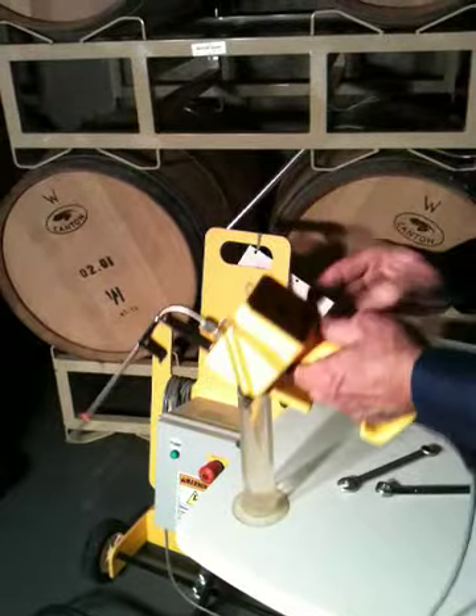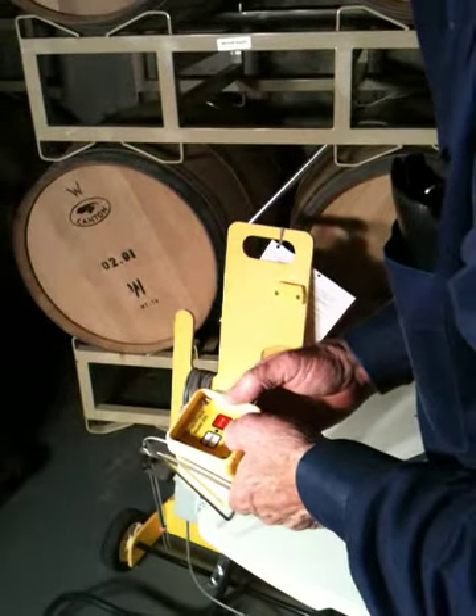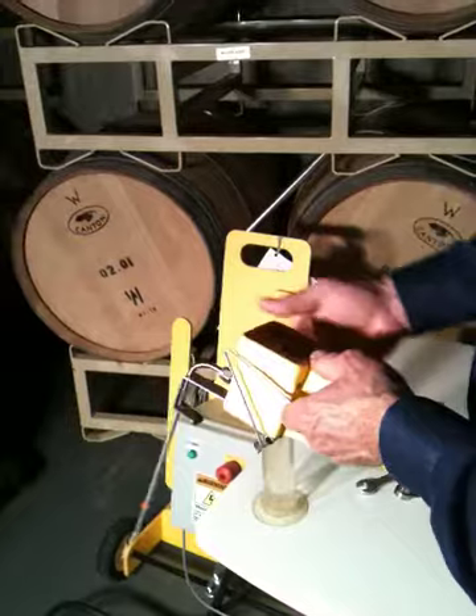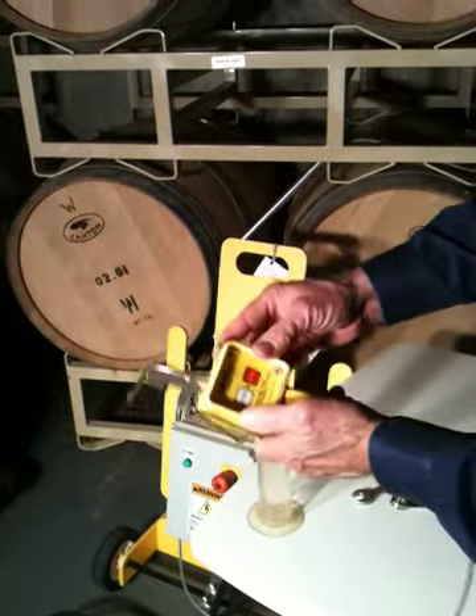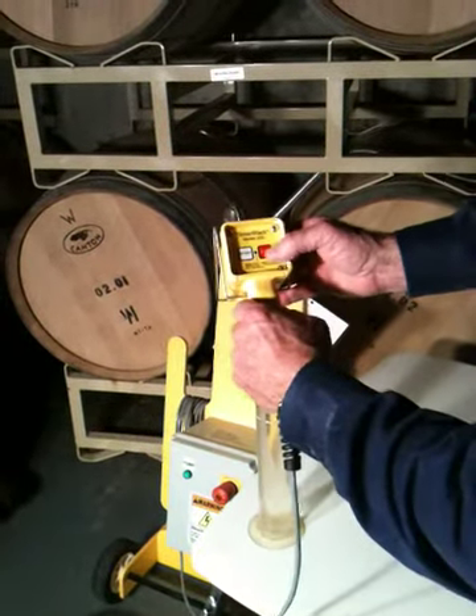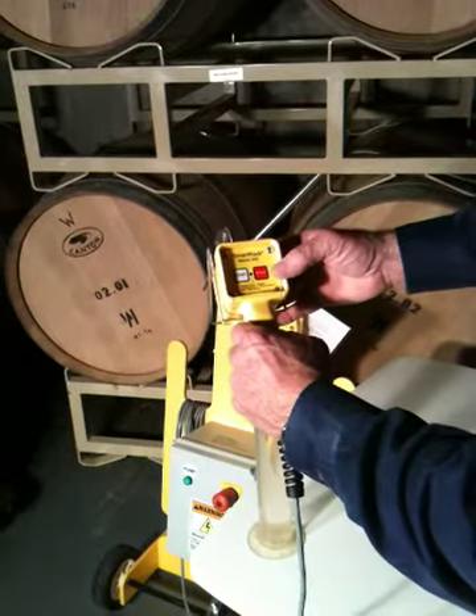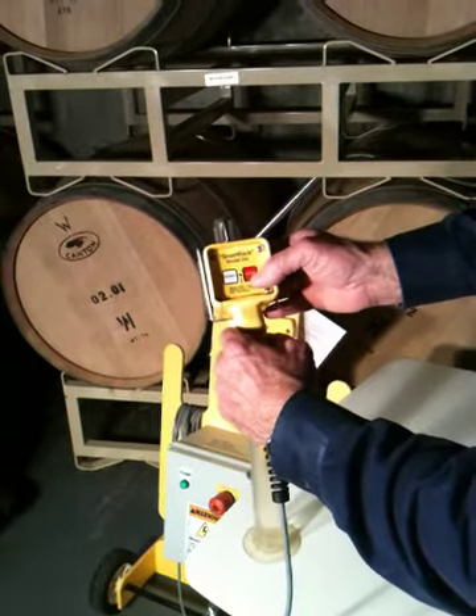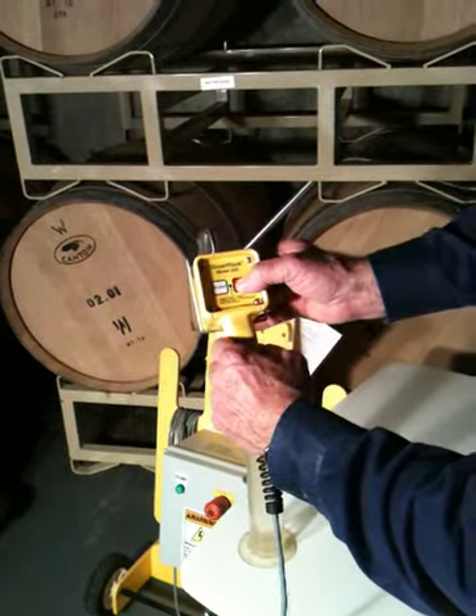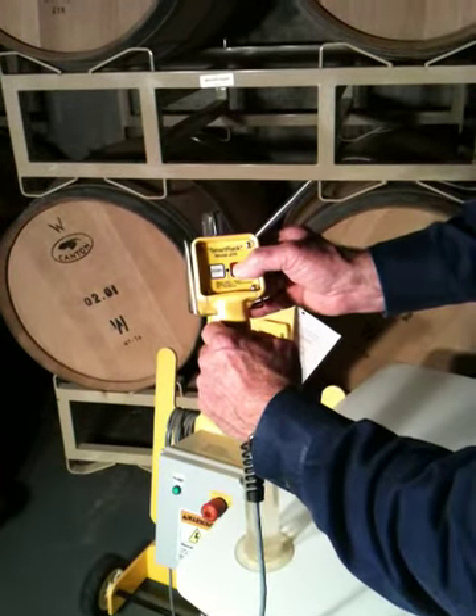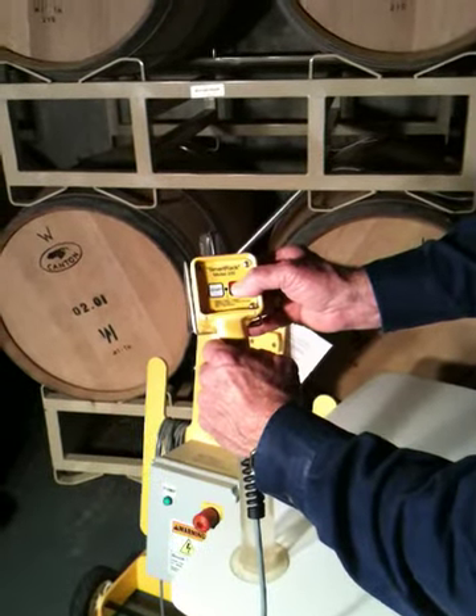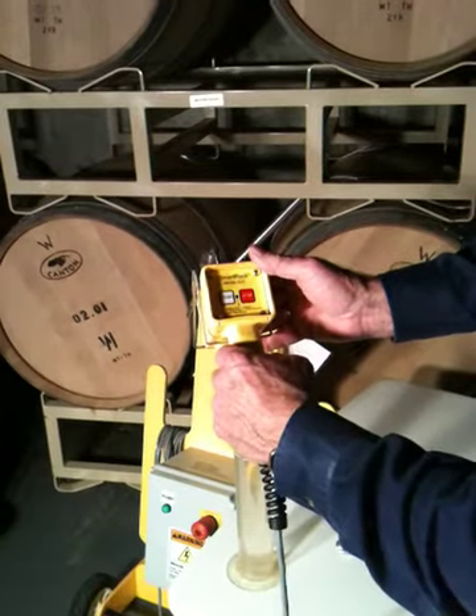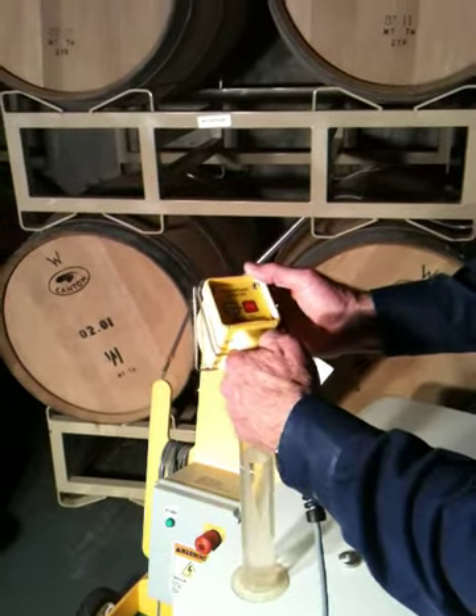Okay, so let's go through one more calibration. Actually, we've already calibrated. We see it's operating correctly, but let's just go through and demonstrate how to do the calibration and leak test again. You've got to be in the calibrate mode to get into the leak test. So once again, the green light is on. It's ready to operate. We press and hold the stop button. The red LED flashes red 5 times and stops. There you are. So now we're in the calibrate mode. Sorry, we're in the leak test mode.